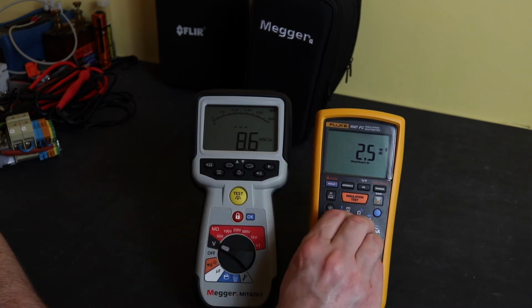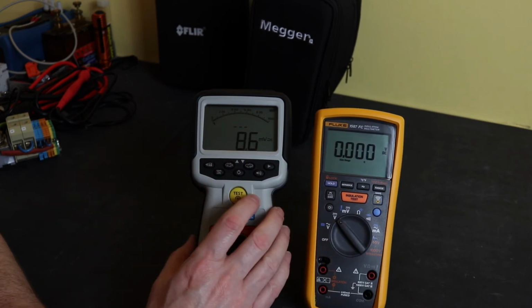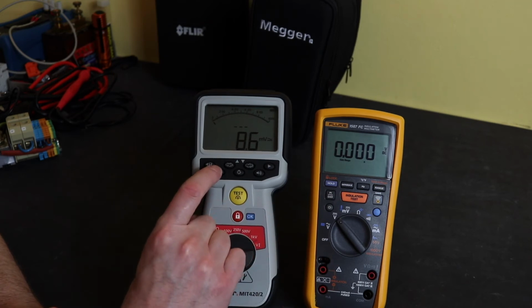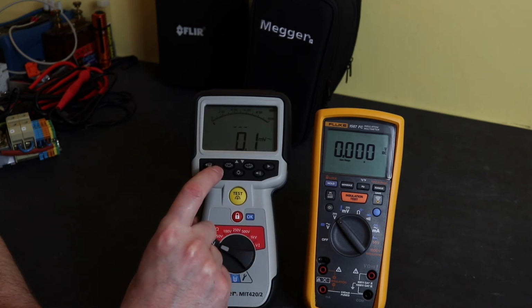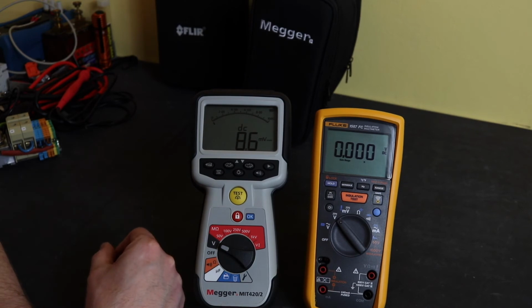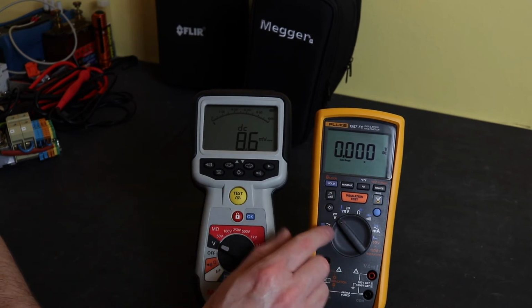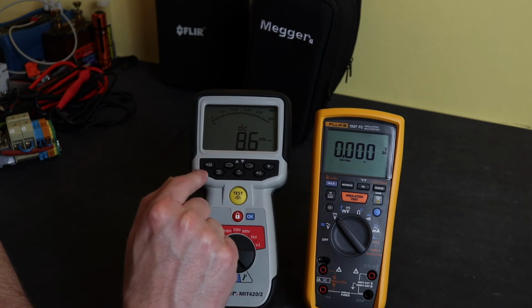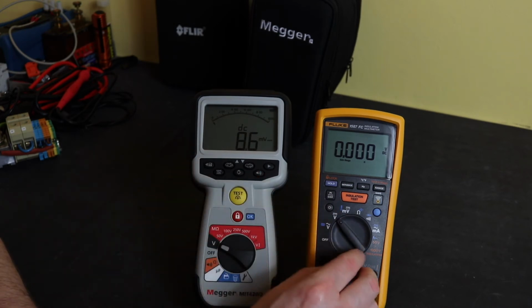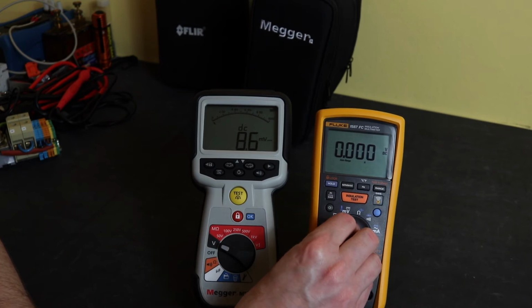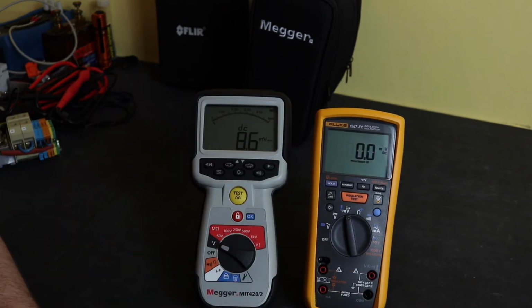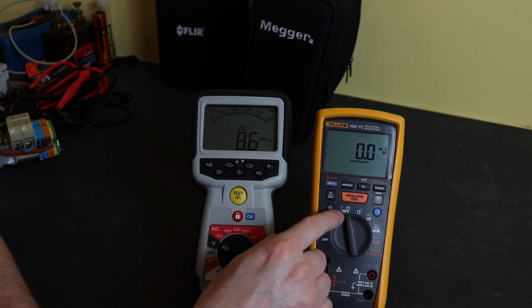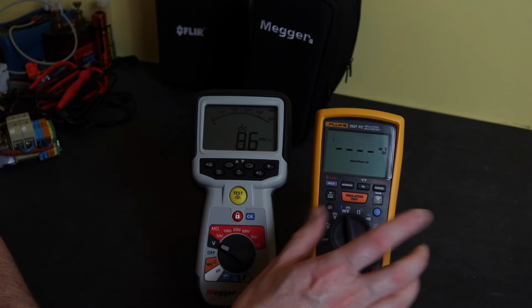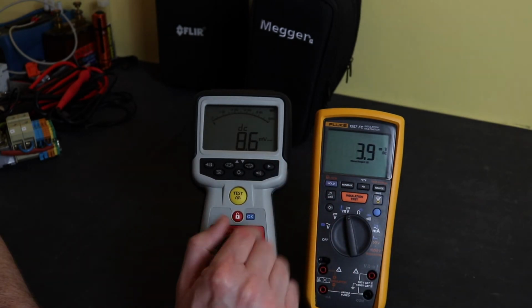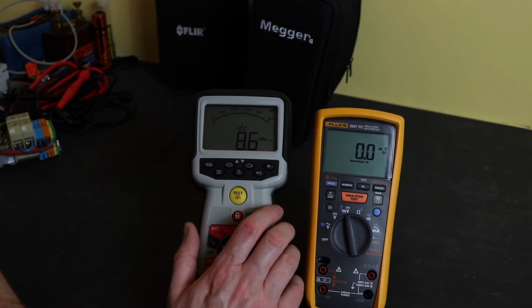Next function switch is volts DC. To get volts DC on the Megger, you just page through. That's actually AC volts there. That's actually DC millivolts there. The DC millivolts and voltage is all on one function on the Megger. To get DC millivolts on the Fluke, you have a separate function off the rotary switch there. And in that position, you also have access to the temperature function just there, which you don't have any temperature measurement capability on the Megger instrument here.